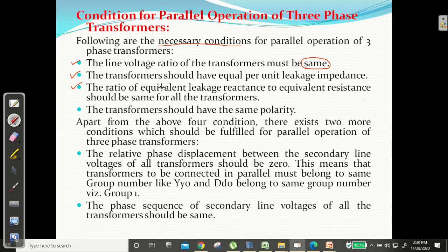Third, the ratio of equivalent leakage reactance to equivalent resistance should be same for all transformers. This condition is not mandatory, but it should be there. If not satisfied, the power factor will be different, so sharing will be different.